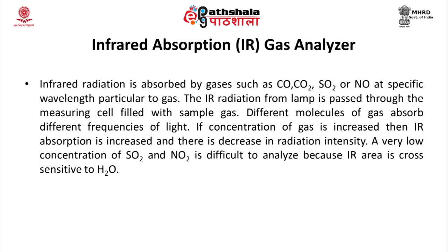Infrared radiation is absorbed by gases such as carbon monoxide, carbon dioxide, sulfur dioxide, and nitrogen dioxide at a specific wavelength particular to each gas. IR radiation from the lamp is passed through a measuring cell filled with the sample gas; different molecules absorb different frequencies of light. If the concentration of the gas increases, IR absorption increases and there is a decrease in radiation intensity. Very low concentrations of SO2 and NO2 are difficult to analyze because the IR area is cross-sensitive to water molecules.